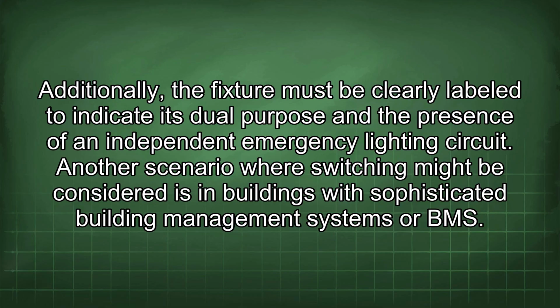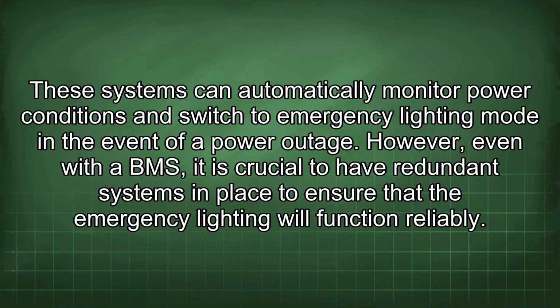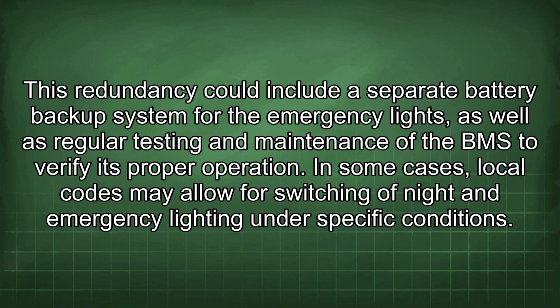Another scenario where switching might be considered is in buildings with sophisticated building management systems, or BMS. These systems can automatically monitor power conditions and switch to emergency lighting mode in the event of a power outage. However, even with the BMS, it is crucial to have redundant systems in place to ensure that the emergency lighting will function reliably. This redundancy could include a separate battery backup system for the emergency lights, as well as regular testing and maintenance of the BMS to verify its proper operation.